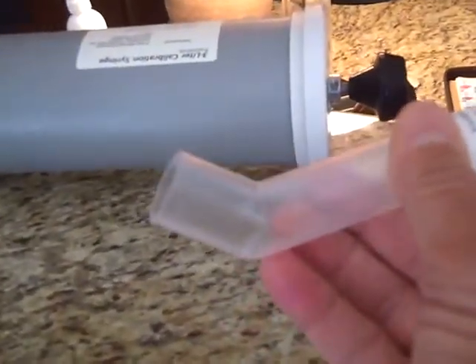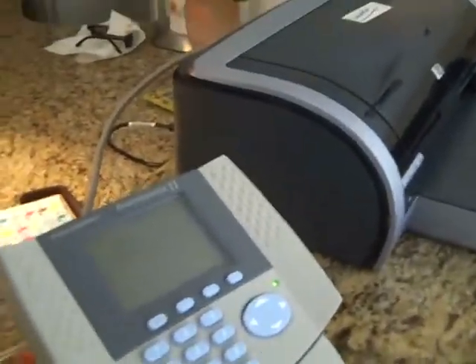And what you're going to actually have the patient do is take a deep breath, and they're going to blow in this end, not the flanged end, but the other end, this end right here. So what I tell them to do is imagine that you've got a birthday cake and you want to blow out all of the candles. So they're going to take a real deep breath and put their mouth around this end and blow out very hard and keep pushing. And the trick to this is that the person has to blow out for 6 seconds in the machine for it to take the test, and if it's not long enough, the machine will tell you the test was not accepted.